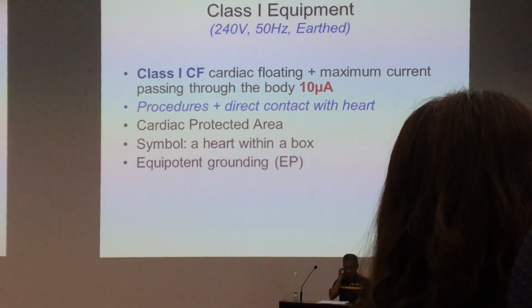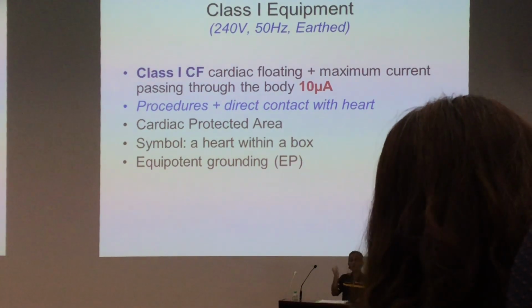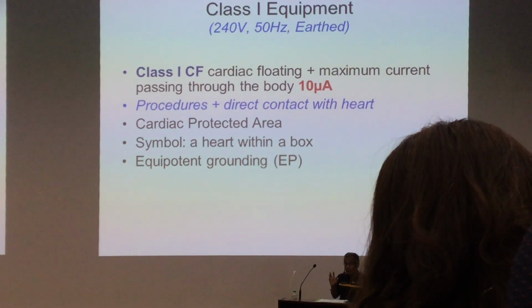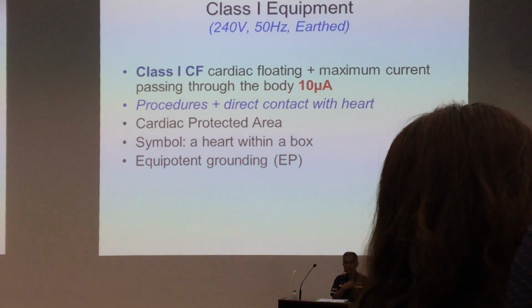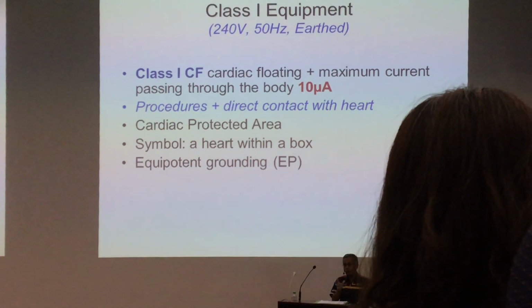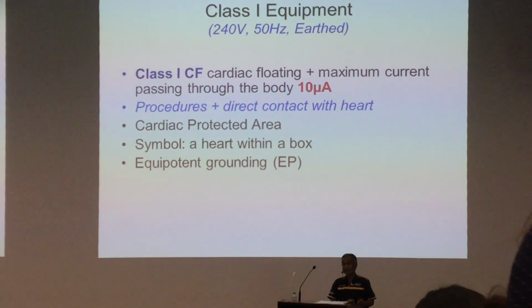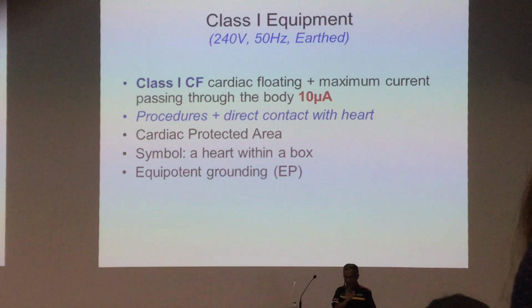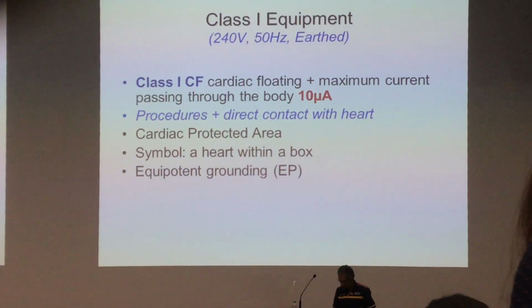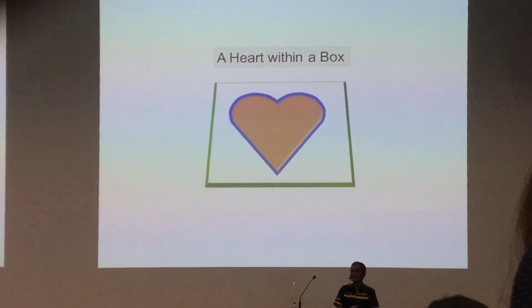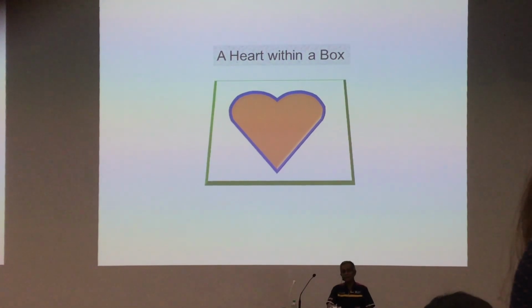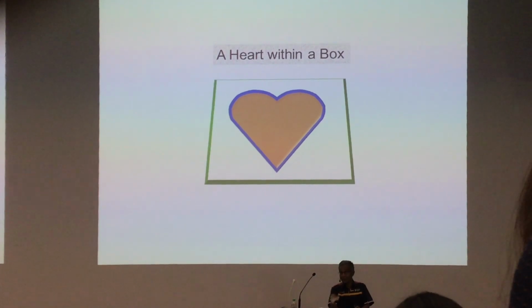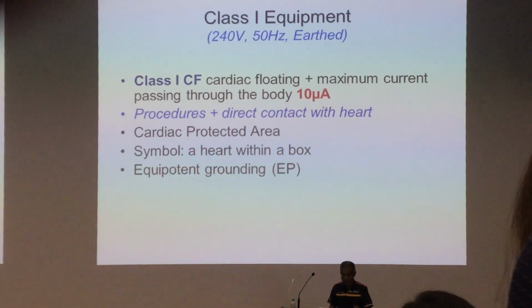So this is standard. For example, in CV lab, CABG OT, or any area where you are going to perform CVP insertion, pacemaker, angiogram, or all those things related directly to the heart. So this is the area where you should use. Area with electrical supply belonging to class 1 CF. The current allowed is 10 microamp. The symbol is this, the heart symbol. So if you look at the monitor, they put this label. On monitor equipment, at the back, you can see this label, which means this machine belongs to class 1 CF.